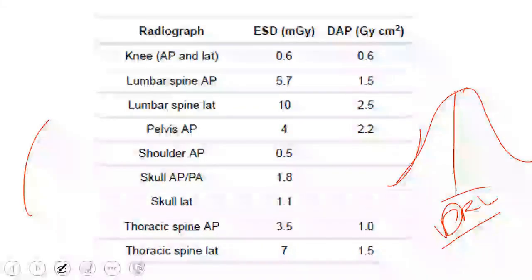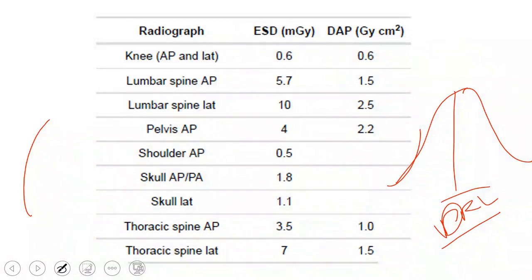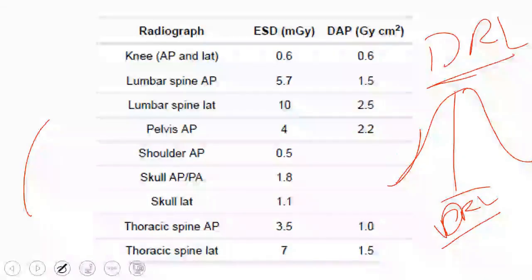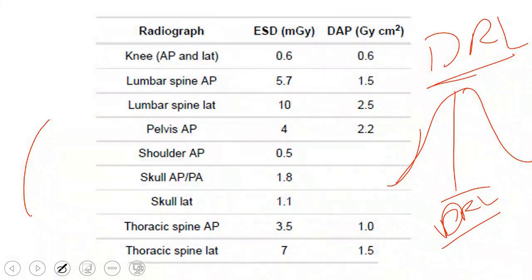and conduct a second survey on the same new parameters and collect new data, and my new diagnostic reference level, DRL, will be established. This DRL will be in place for 3 years, and for me, this DRL will be valid. After 3 years, I will start this survey again and check on my cases to see how the operators and the staff adhered to the parameters, and whether the doses are still within my limit or have exceeded it.